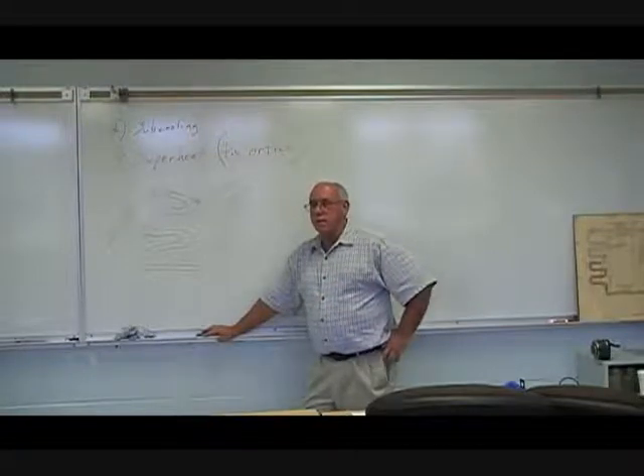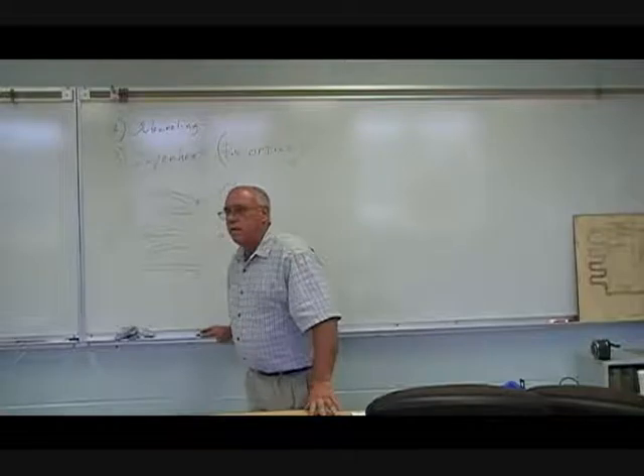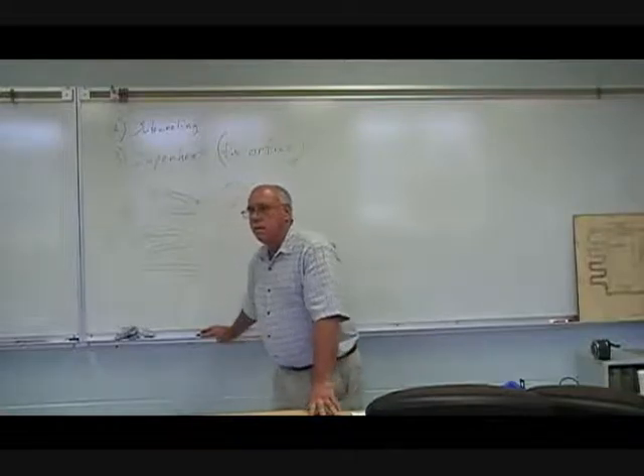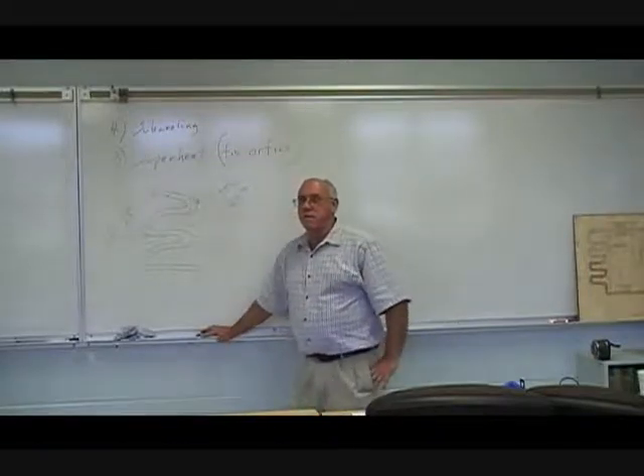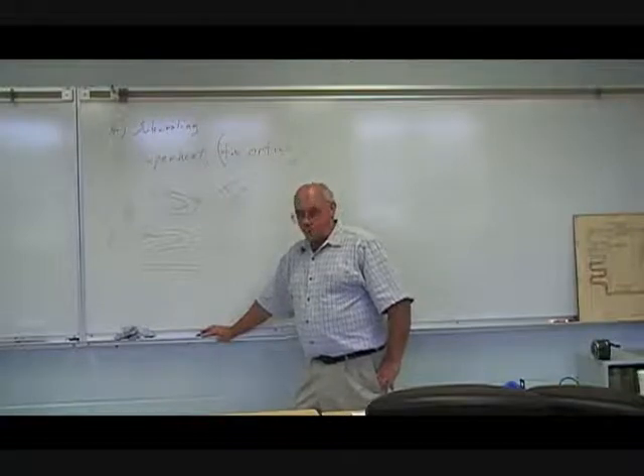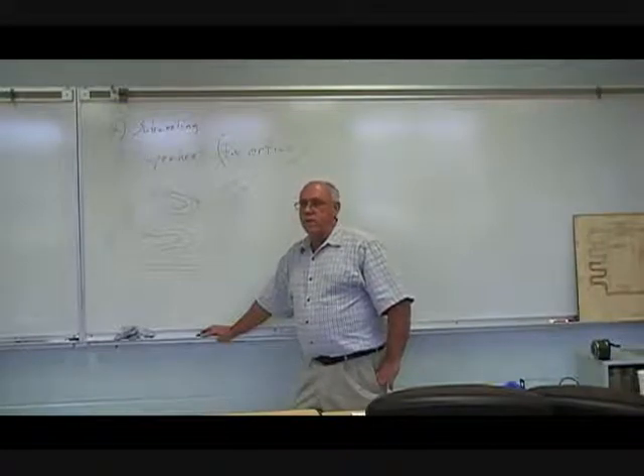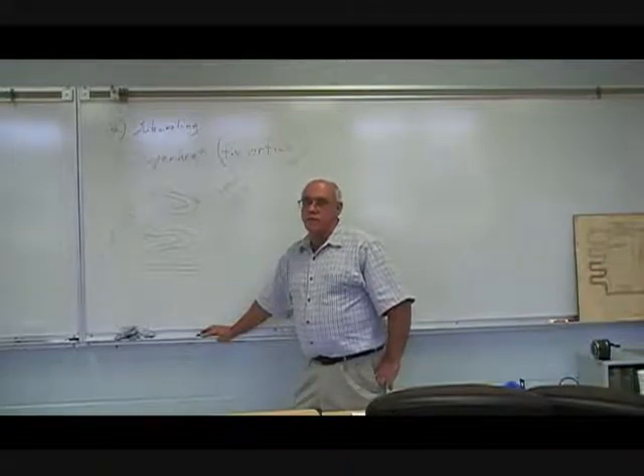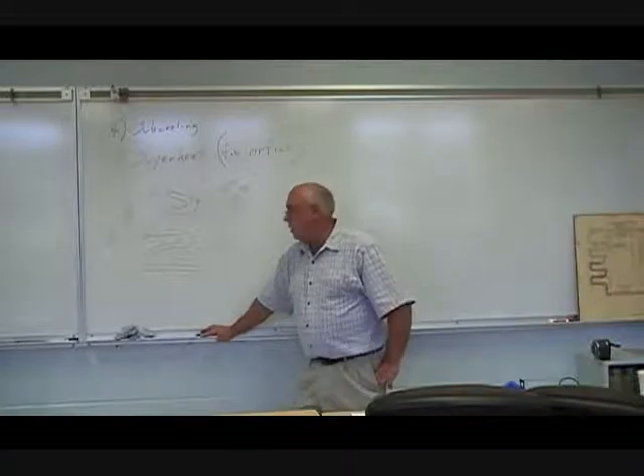I've got a question. I've got two units outside my house, one's a three ton, one's a two ton. Should my pressures be the same? Talking about tonnage? Should the pressures be the same or different? The pressures make no difference on the tonnage. So regardless if I've got three ton or two ton, I'm going to measure both of them should be the same. Tonnage makes no difference. It's just you're moving more gas with the higher tonnage. The boiling points don't change. That's a good question.